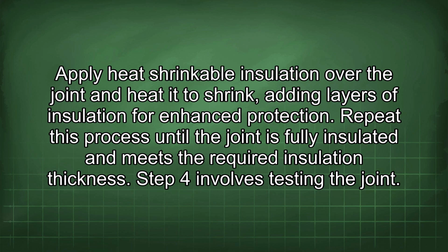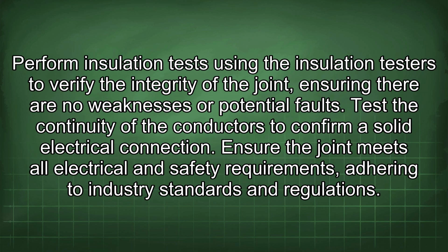Step 4 involves testing the joint. Perform insulation tests using the insulation testers to verify the integrity of the joint, ensuring there are no weaknesses or potential faults. Test the continuity of the conductors to confirm a solid electrical connection. Ensure the joint meets all electrical and safety requirements, adhering to industry standards and regulations.